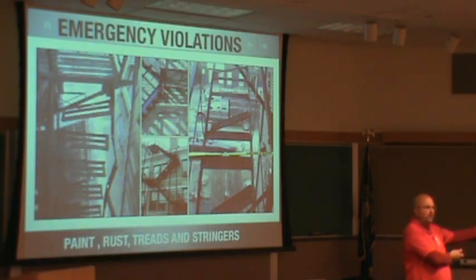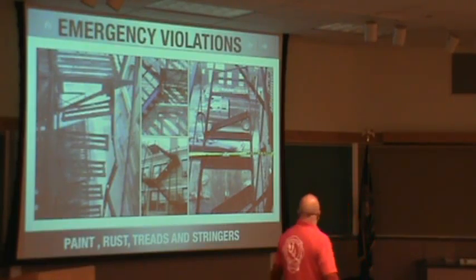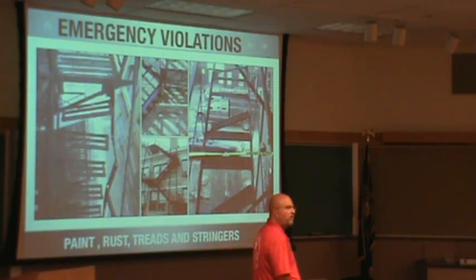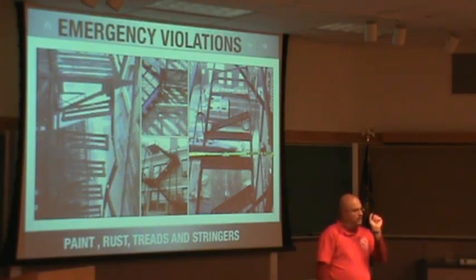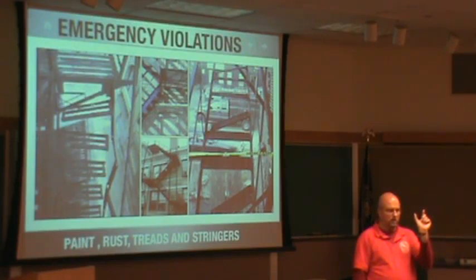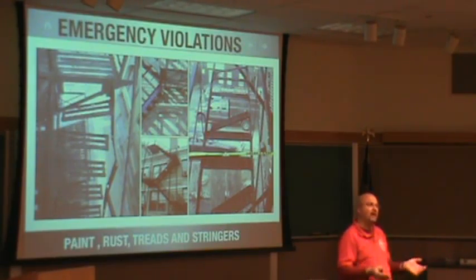And if they replace it — any load test requirement for a 100% replacement? No, because the engineer has already given you the documentation for the permit process. During the refurbishment, on the stair treads, if the thickness of the metal has degraded, you have to replace the stair — any tread that's bad. But fire escapes are very forgiving. A quarter-inch piece of steel will grow to one inch of rust. When you have rust between the connections and you clean it, there's still plenty of meat left — 80 to 85% of the steel is still there.